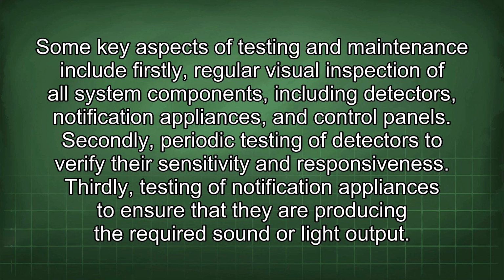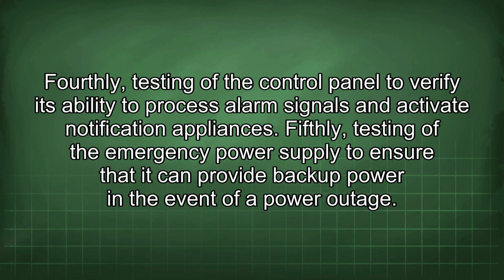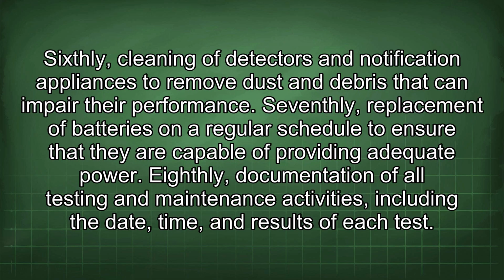Thirdly, testing of notification appliances to ensure that they are producing the required sound or light output. Fourthly, testing of the control panel to verify its ability to process alarm signals and activate notification appliances. Fifthly, testing of the emergency power supply to ensure that it can provide backup power in the event of a power outage. Sixthly, cleaning of detectors and notification appliances to remove dust and debris that can impair their performance.